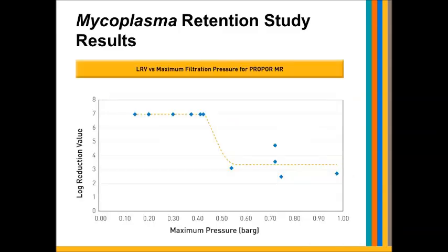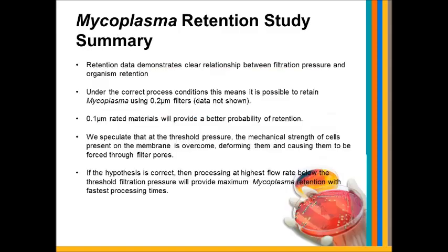With this particular organism, and the way it was grown, and with the challenge conditions that we imparted, we saw a large drop-off in retention from 10 to the 7th at about half a bar of pressure. And basically, the retention data demonstrates what we think is a clear relationship with filtration pressure.